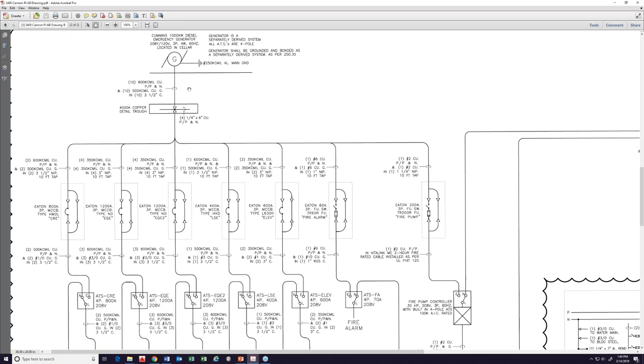It's almost the exact same thing as when you have a feeder. For example, you have an 800-amp feeder. 240.21 allows you to tap. You have the 10-foot tap rule option, or the 25-foot tap rule option, which is one-third of the upstream device. And this is following the same concept.